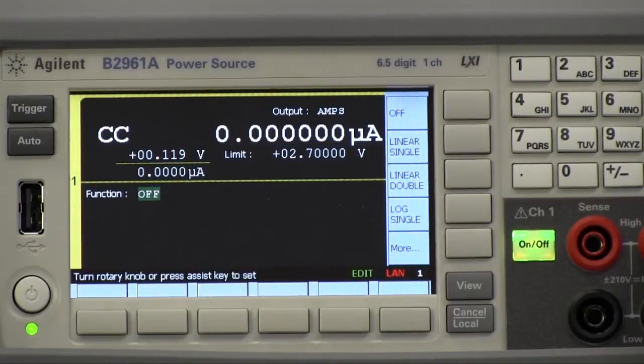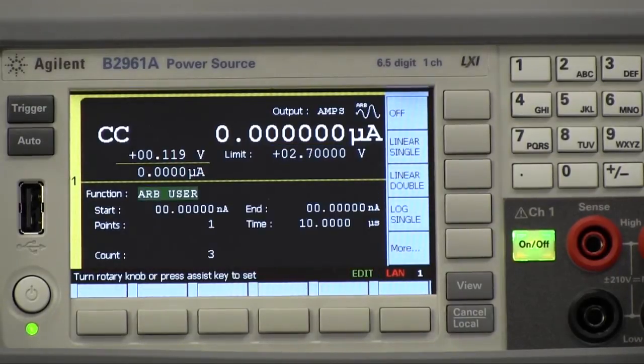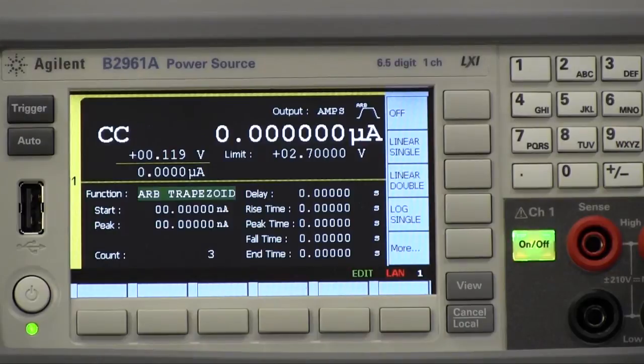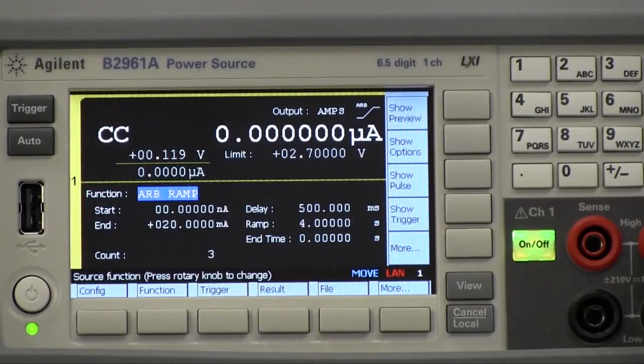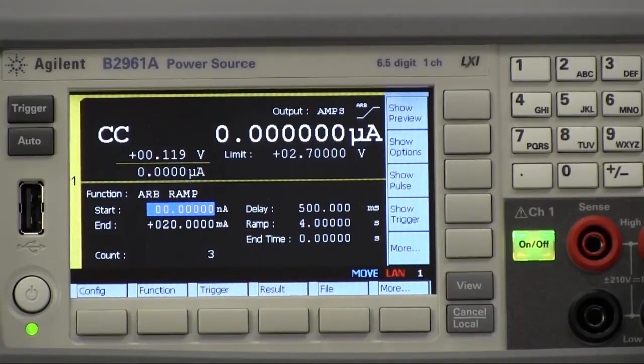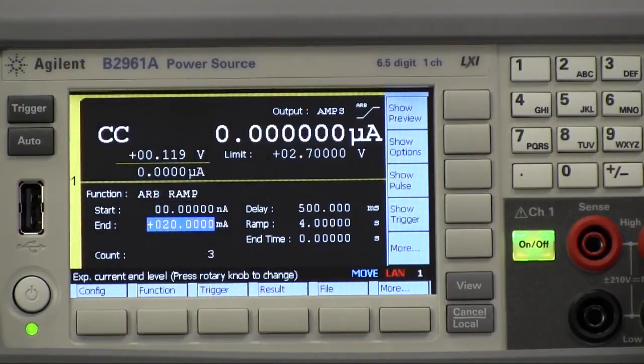Now I'm going to move down to my functions and move down to ramp. Select ramp. I'm going to go ahead and start. So 0 amps is fine. We're actually going to go up here to 20 milliamps. So that also is good.